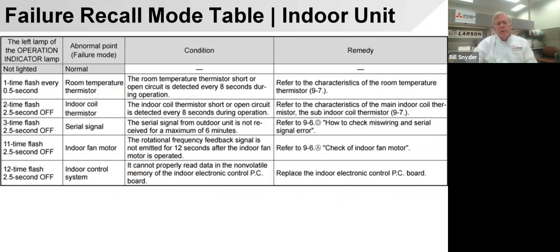And in there, it will give you a failure mode. And where you would get this is on the mylinkdrive.com. You just type that in Google and it'll pop up. Don't need any kind of a password to let you right in. You pick the M series. If you're working on M series, you pick the model number of the outdoor unit or the indoor unit, and you'll get this type of a flash code.